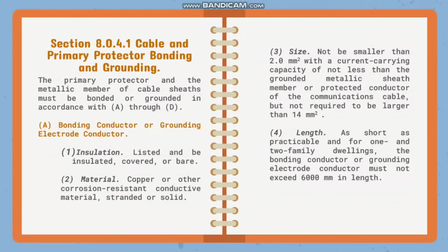Section 8.0.4.1, Cable and Primary Protector Bonding and Grounding. The primary protector and the metallic member of cable sheaths must be bonded or grounded in accordance with A through D. So, ang i-discuss lang po natin is yung A, which is yung bonding conductor or grounding electrode conductor. So, for the insulation, listed and be insulated, covered or bare. For the material, copper or other corrosion-resistant conductive material, stranded or solid. For the size, not be smaller than 2.0 mm squared with a current carrying capacity of not less than the grounded metallic sheath member or protected conductor of the communications cable, but not required to be larger than 14 mm squared.